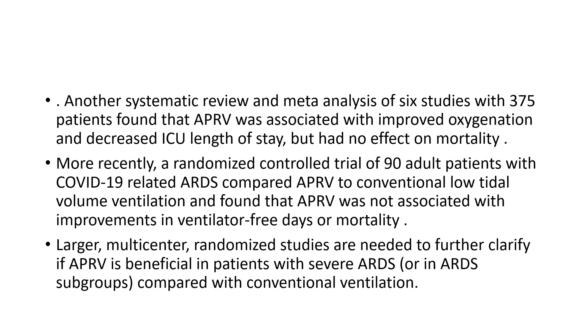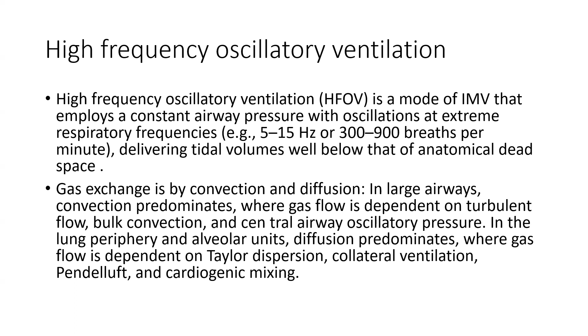High frequency oscillatory ventilation is a mode of invasive mechanical ventilation that employs constant airway pressure with oscillations at extreme respiratory frequencies, delivering tidal volume well below the anatomical dead space. So gas exchange is by convection and diffusion. In larger airways, convection predominates, where gas flow is dependent on turbulent flow, bulk convection, and central airway oscillation pressure. In the lung periphery and alveolar unit, diffusion predominates, where gas flow is dependent on Taylor dispersion, collateral ventilation, pendelluft, and cardiogenic mixing.